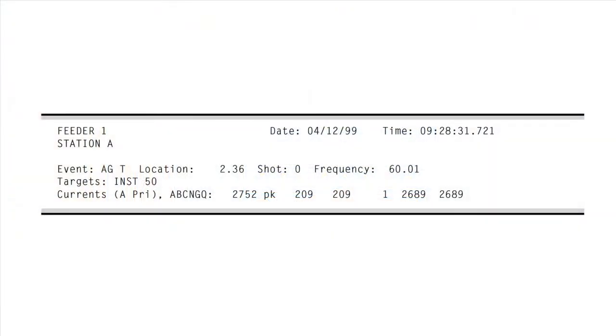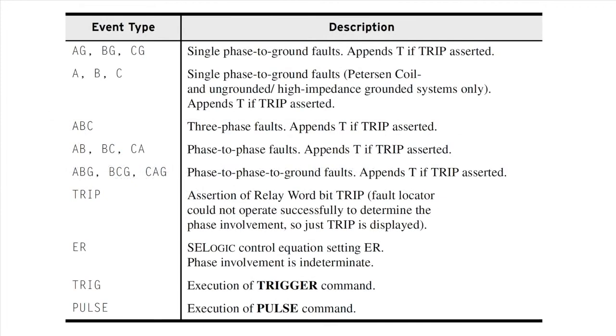Fault locator. The SEL 351A provides an accurate estimate of fault location even during periods of substantial load flow. The fault locator uses fault type, replica line impedance settings, and fault conditions to develop an estimate of fault location without communications channels, special instrument transformers, or pre-fault information. This feature contributes to efficient dispatch of line crews and fast restoration of service. The fault locator requires 3-phase voltage inputs.